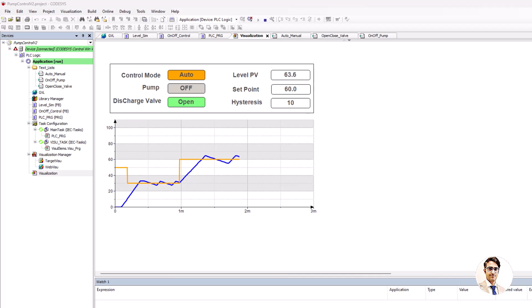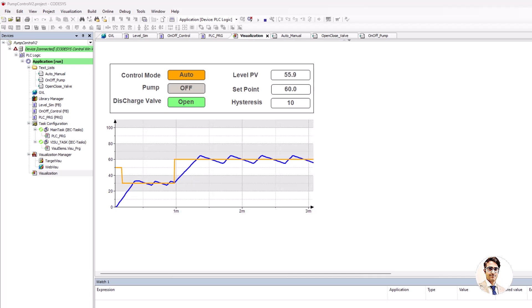We can see that the level present value oscillates around the set point based on the hysteresis. For example, now the set point is 60 and the hysteresis is 10, so the level oscillates between 55 and 65.